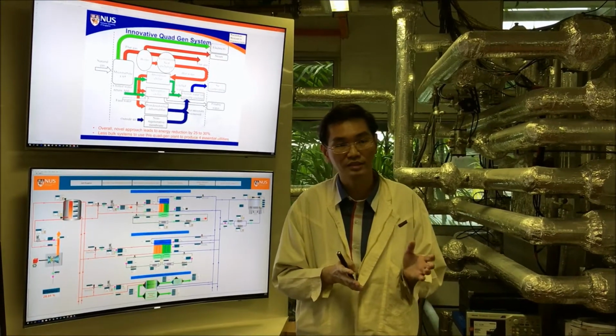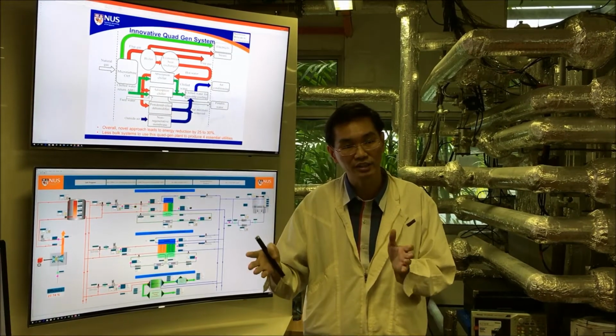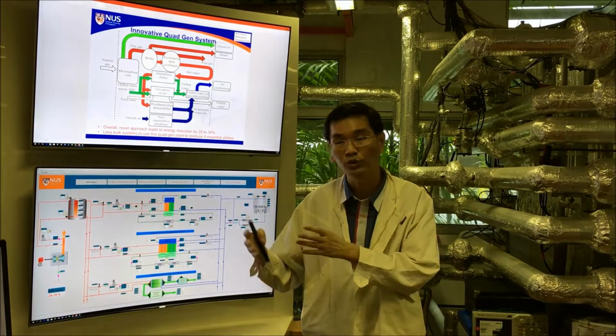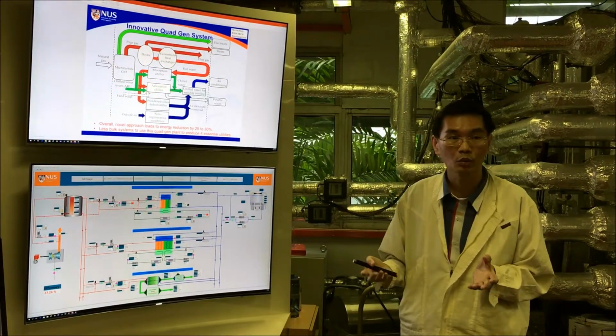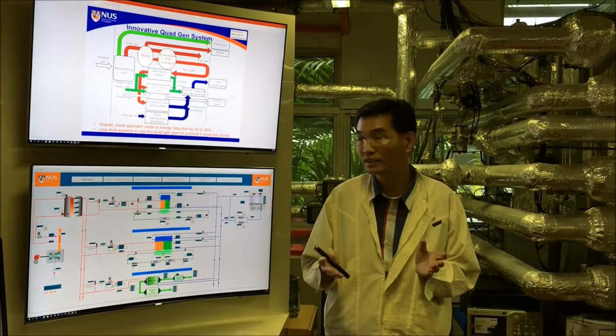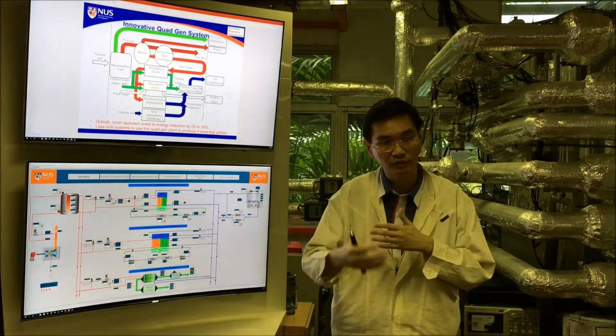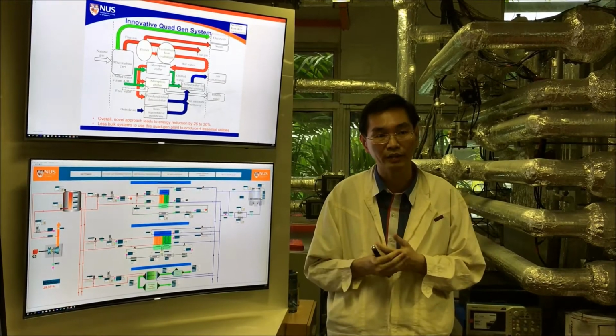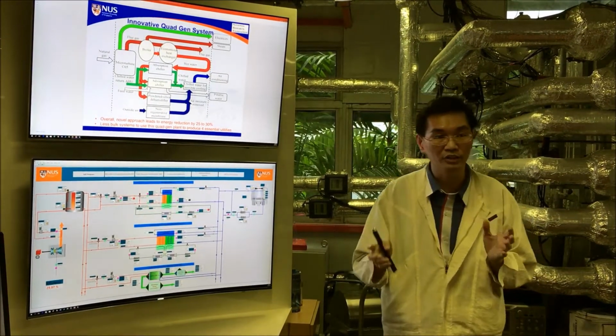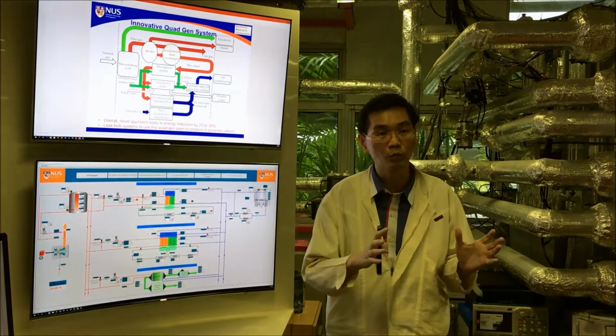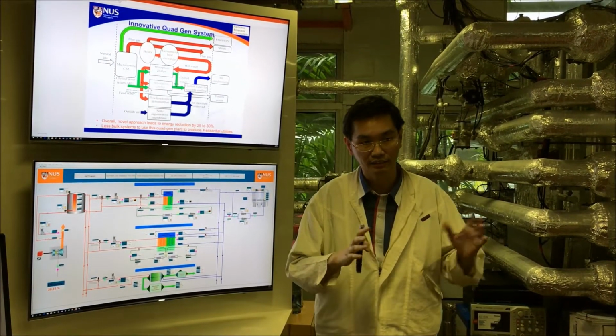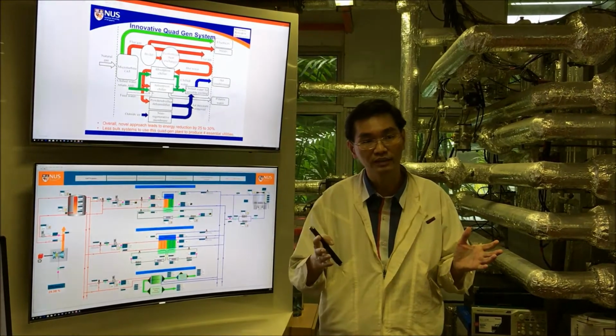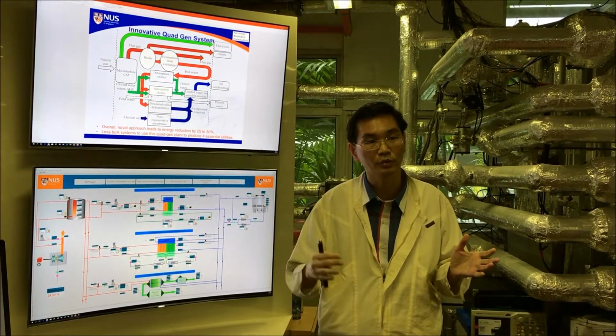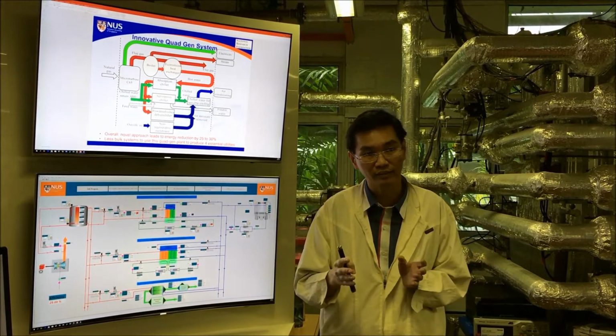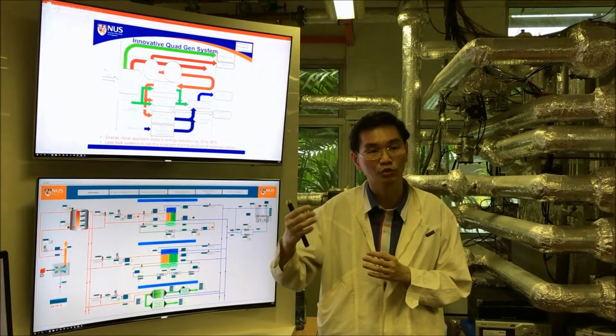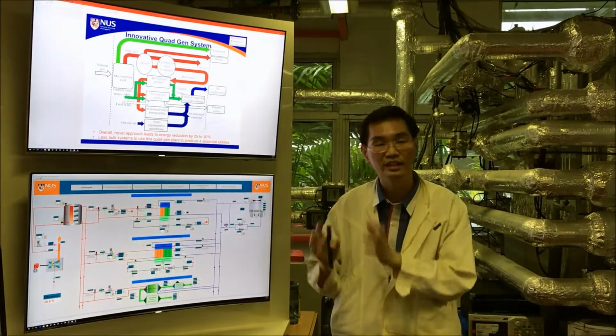The byproduct of this system is that you can feed wastewater into the AD chiller and it will clean up this wastewater to produce potable water, right? Potable drinking water that is of very high quality. So in this system here, we also have simultaneously incorporated 2 other very impactful technologies. Here we have the membrane technology plus the super absorbent dehumidifier to remove the moisture of the air inside the plant, so that the chilled water that's provided to the AHU can be raised at a higher temperature. From 6 to 8, we can operate it at a higher temperature, about 13 to 15, because now the chilled water only needs to do sensible cooling.